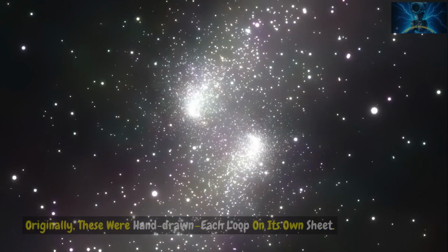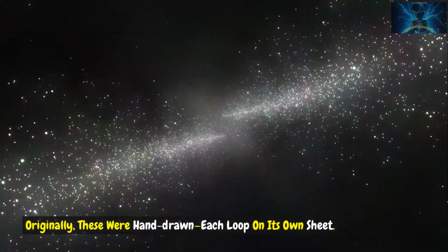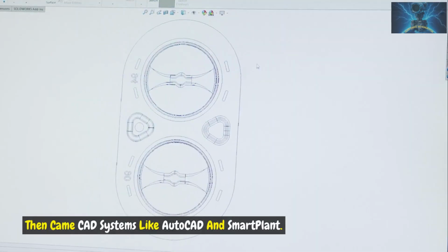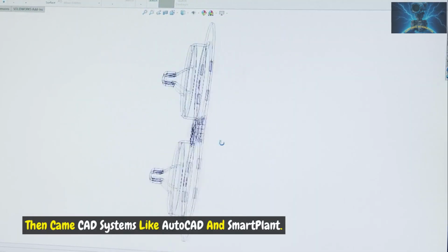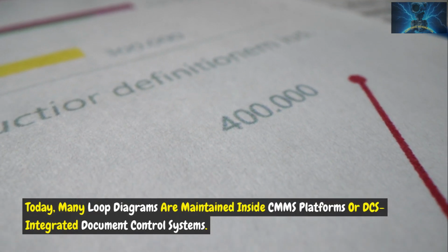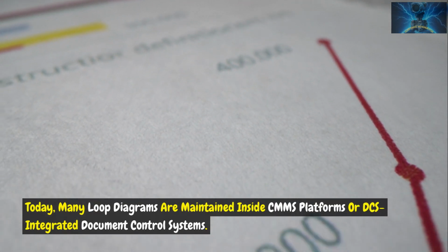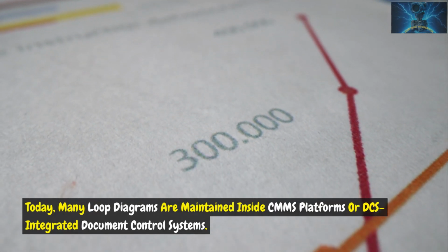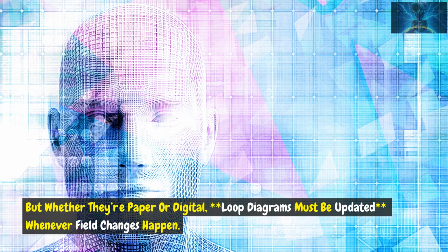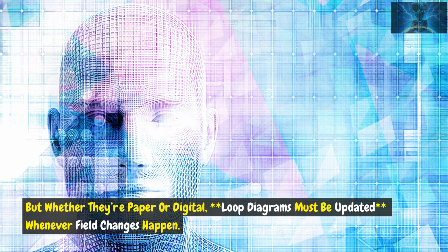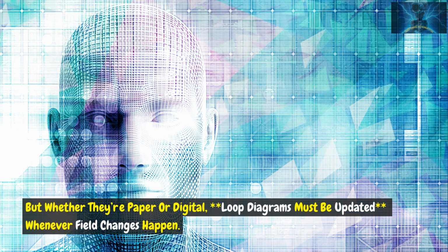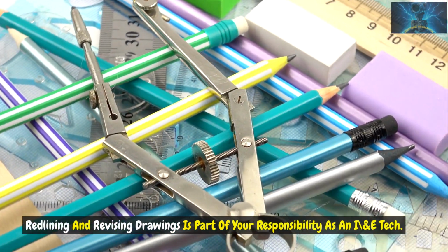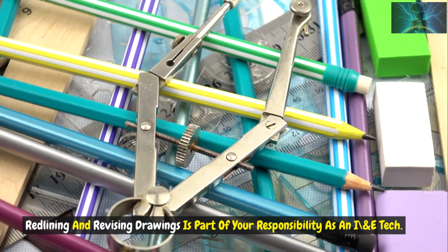How are loop diagrams created and maintained? Originally, these were hand-drawn, each loop on its own sheet. Then came CAD systems like AutoCAD and SmartPlant. Today, many loop diagrams are maintained inside CMMS platforms or DCS integrated document control systems. But whether they're paper or digital, loop diagrams must be updated whenever field changes happen. Redlining and revising drawings is part of your responsibility as an I&C tech.